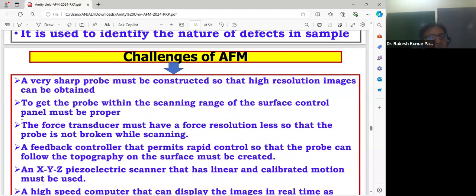The first challenge is that a very sharp probe must be constructed so that a high resolution image can be obtained. This is the first and most important challenge in front of us. Your tip is very sharp and its resolution depends upon its sharpness. This is the reason that the cost of tips is higher. It is a little bit more. And to get the probe within the scanning range, this point is also important.